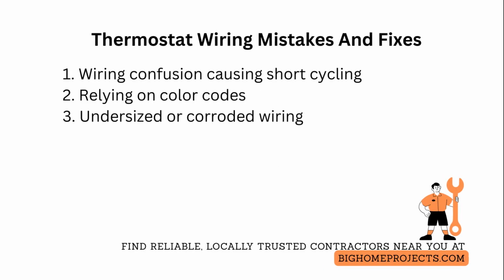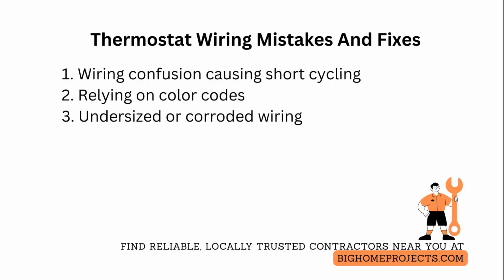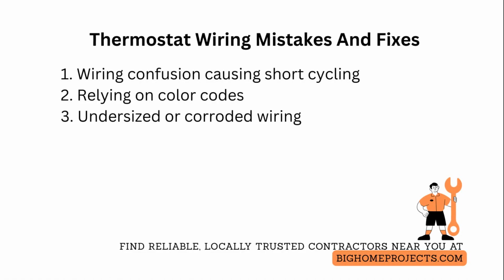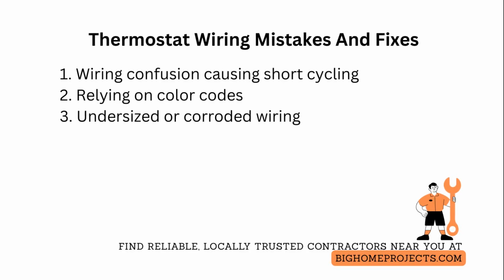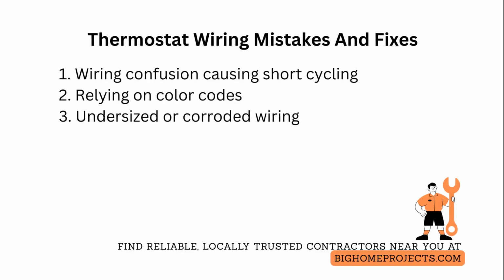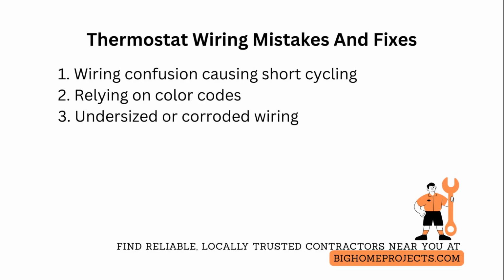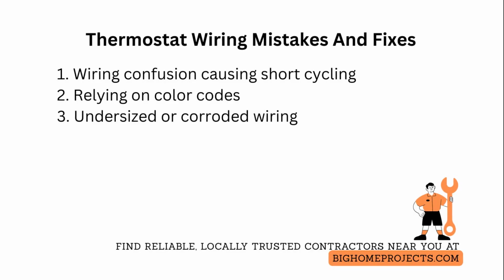One of the biggest issues is thermostat wiring confusion causing short cycling and contactor burnout. Fix by tracing and labeling every conductor, verifying transformer secondary continuity, and using an isolation relay for multi-transformer systems. The second common problem is relying on color codes, which leads to incorrect connections and no cooling. Prevent this by metering every wire and running a dedicated common to the thermostat.